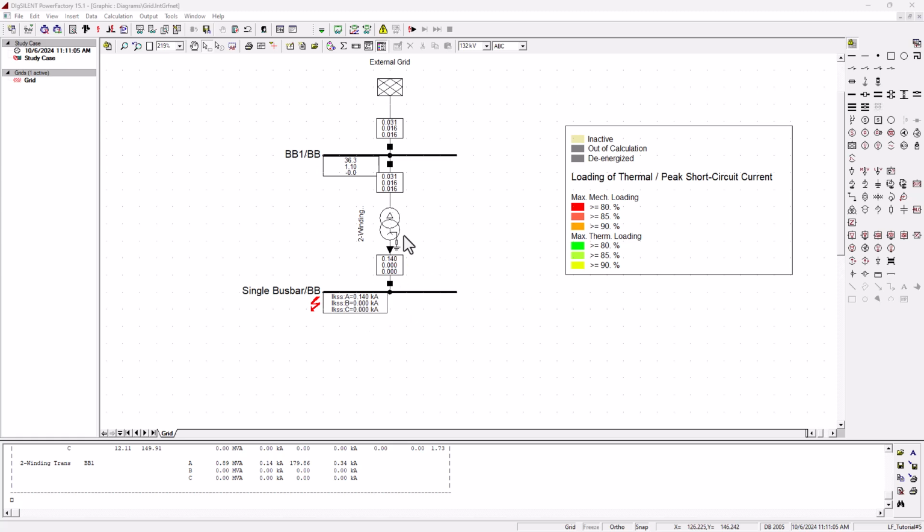But now, if you are dealing with a high voltage system, there is also a method of splitting the network. Basically, instead of just having one line, you're going to split it. That way, your short circuit current is also going to split. It's basically going to be reduced. So these are the basic methods by which you can mitigate your short circuit current.